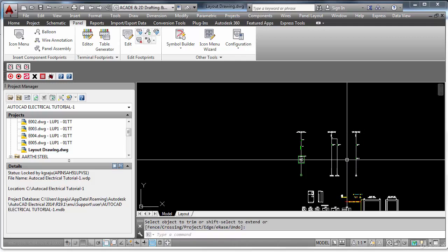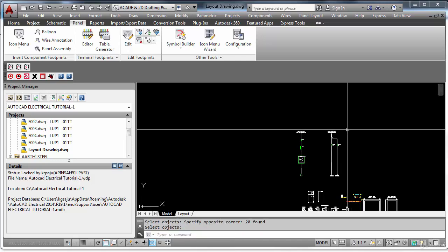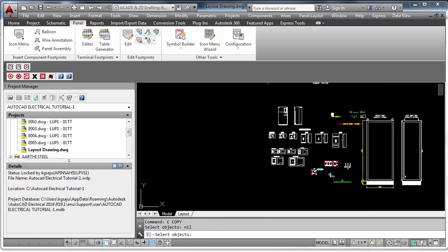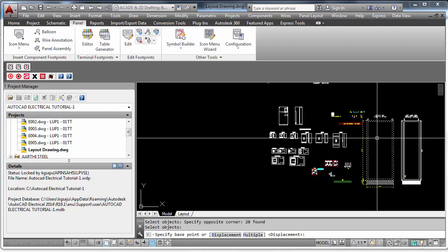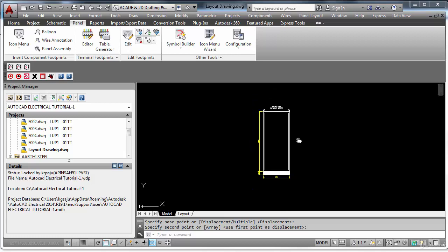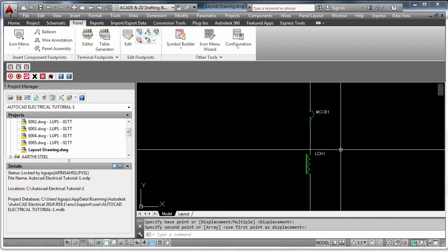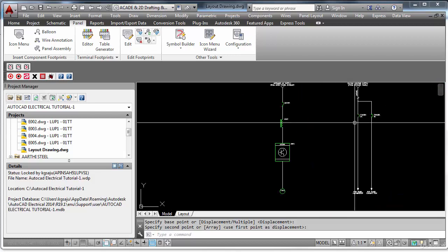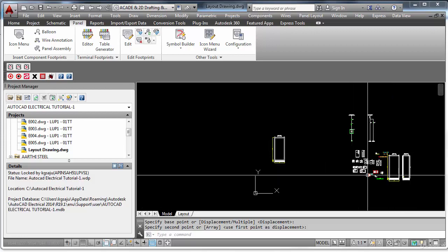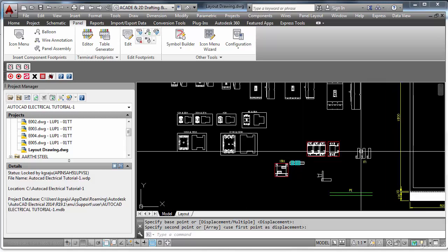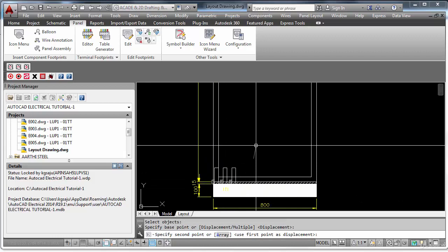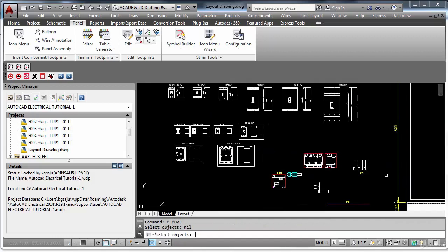So from my library, I have copied all the blocks into a single sheet which is necessary for me, including the panel. Now what I will do is I will create a drawing in this sheet, keeping all the blocks aside. This is my panel, front view of my panel without a door. Now I have to place an MCCB, line choke, drive, and two MCBs. That's all. Incoming supply is from the bottom, I know. So what I will do is I will put few terminals or even bus bars on the bottom side of my panel. These are three incoming bus bars. Okay. I will just a minute.